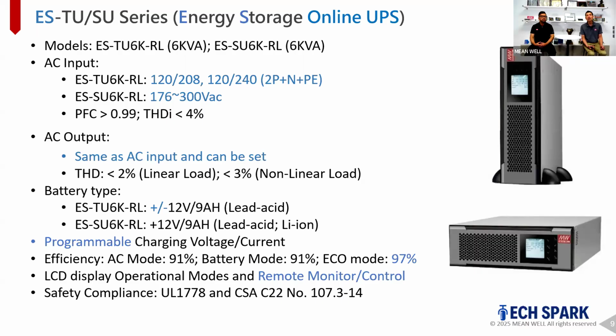It has a PFC of 0.99 because it has the built-in AC to DC converter, and the output is going to be the same as the input since it's a UPS. On top of that, the user can set the output voltage - for example, if your input voltage is 120/208 in the US, you can set the output to be 120/240. The frequency can also change from 50 to 60 hertz or 60 to 50, but that's in a very special operation mode that allows you to do it.